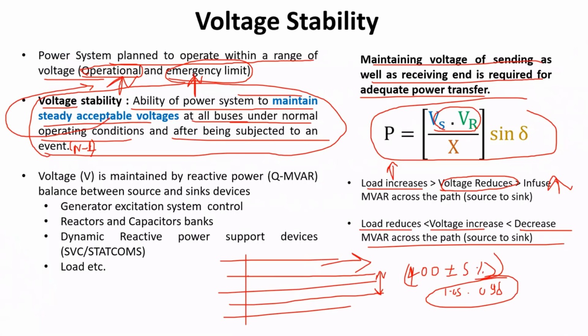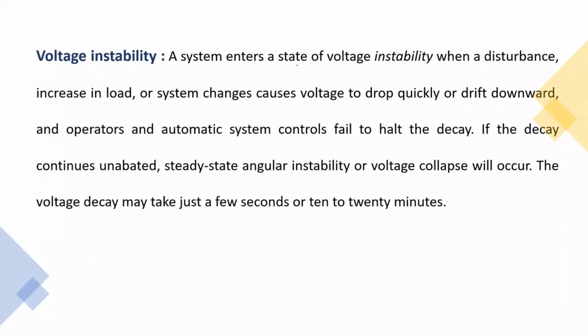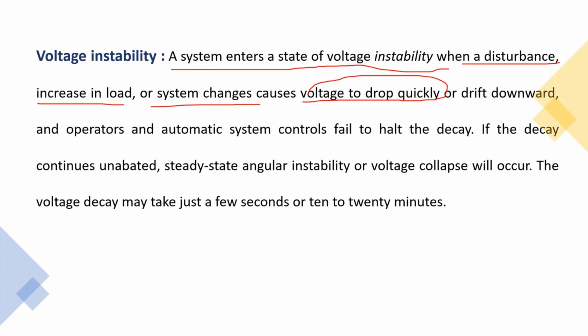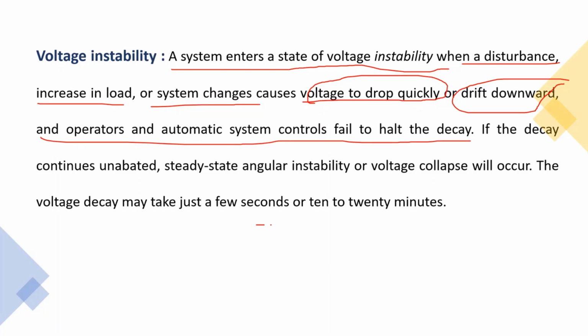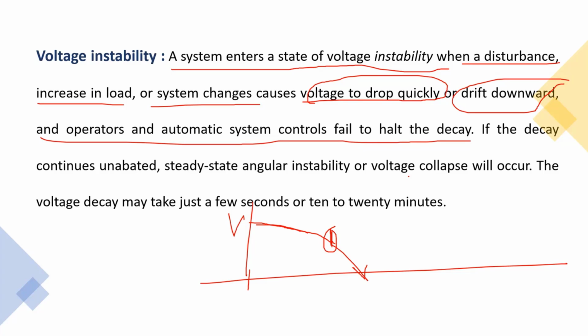And what is voltage stability? We have seen that it is maintaining the voltage within the limits during any normal condition as well as any event. Instability refers to a system entering a state of voltage instability when a disturbance, increase in load, or system change causes the voltage to drop quickly or drift downwards, and operators and automatic control fail to halt that decay. So if the voltage is reducing and you are not able to control this reduction, it goes down and collapses. You don't have enough control over the voltage decay during any kind of change in the system, increase in load, any event, or any drift in the voltage due to a change in the entire load-generation balance or any contingency.